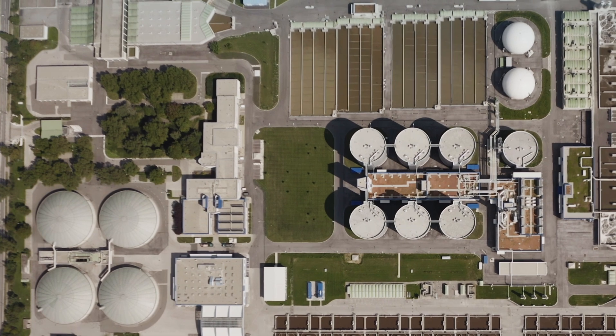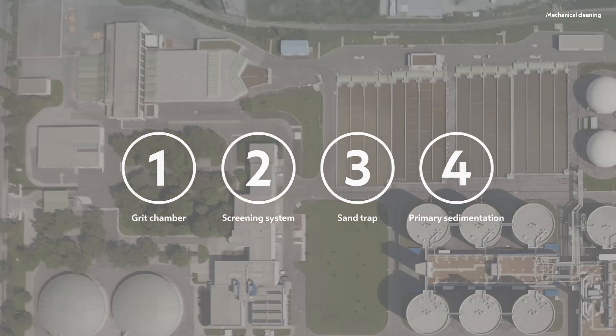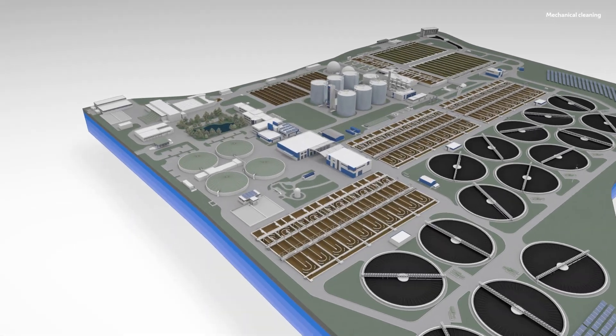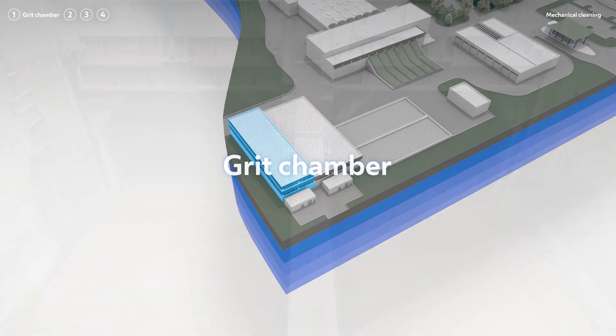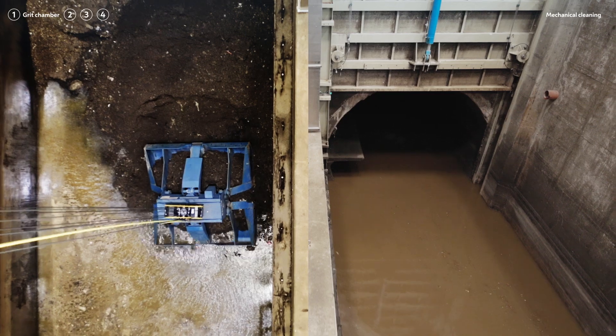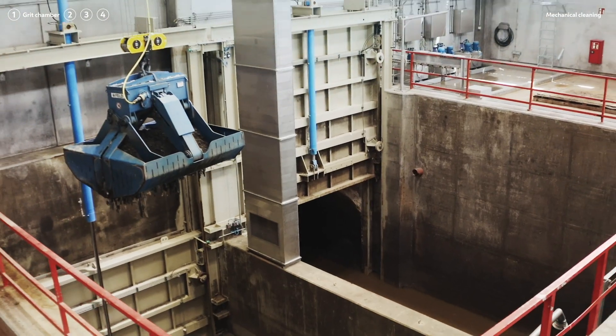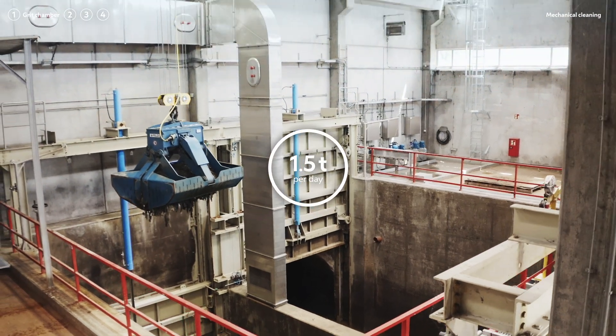Firstly, wastewater passes through four stages of mechanical cleaning. Stage 1 is the grit chamber. Coarse solids, such as stone, settle in a trough at the bottom of the sewer bed. EBS Wien disposes of 1.5 tonnes of sedimented grit every day. This part of the process is very important as it prevents damage to the downstream plant components.